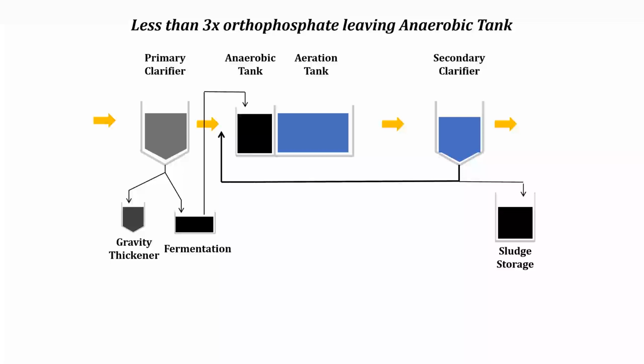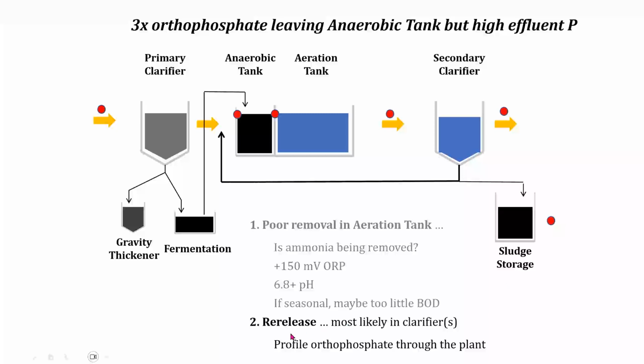More likely, frankly, back to here, I probably should have put the re-release as the first. More likely, if the phosphorus removal was, you were getting satisfactory phosphorus removal and it started going bad, it could very well be that it was re-release.